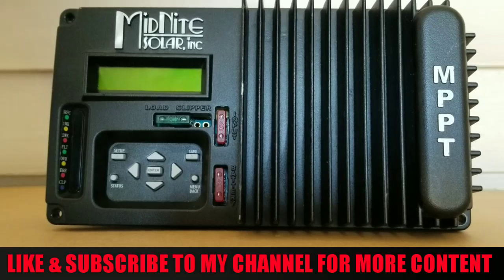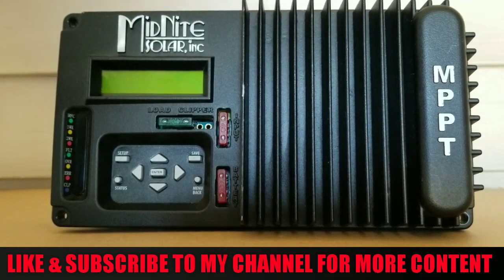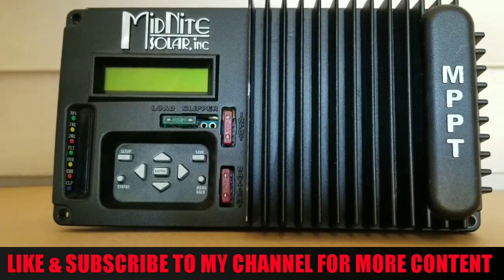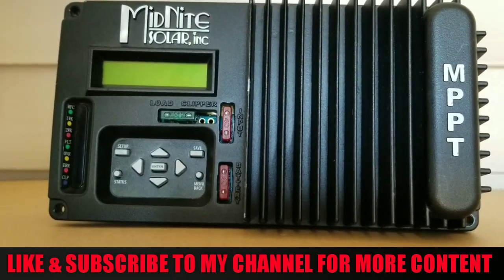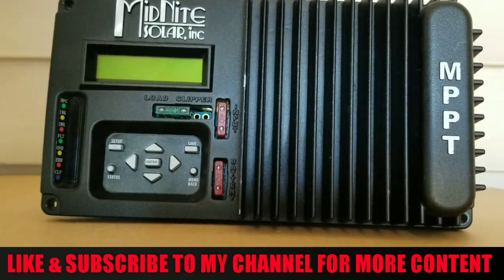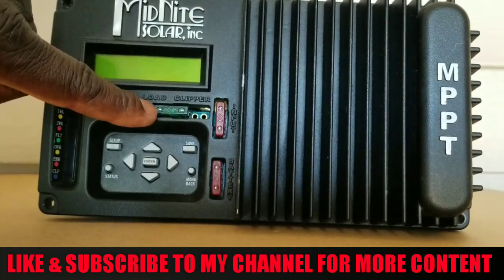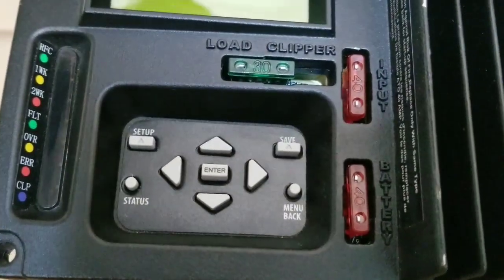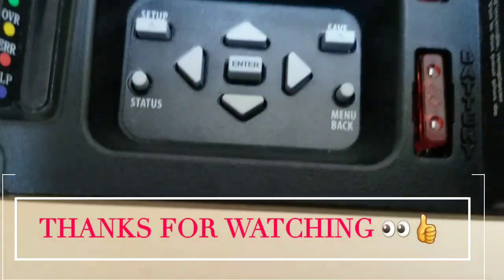Today's video is Part 2 of the MidNite Solar Incorporated Kid charge controller — the 30 amp MPPT charge controller made by MidNite Solar. On the front you can see a load, a 30 amp fuse, a 40 amp fuse on the PV inputs, and another 40 amp going to the batteries.